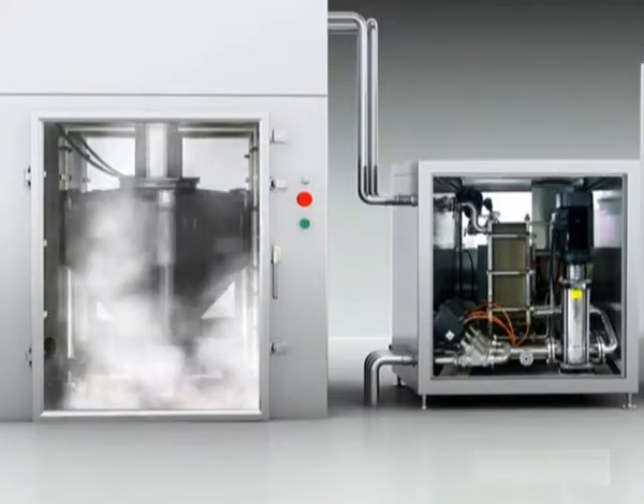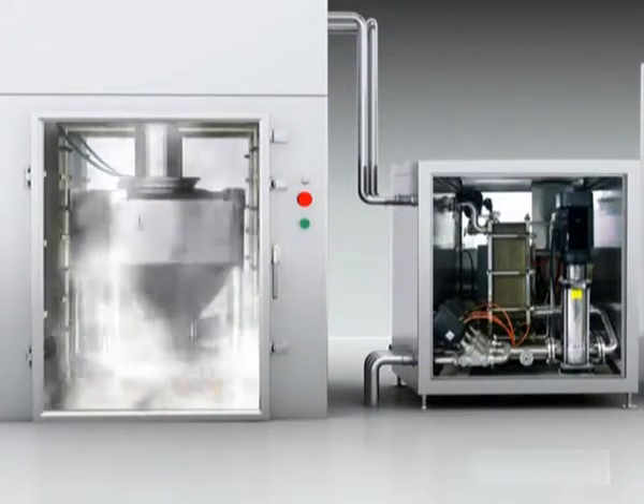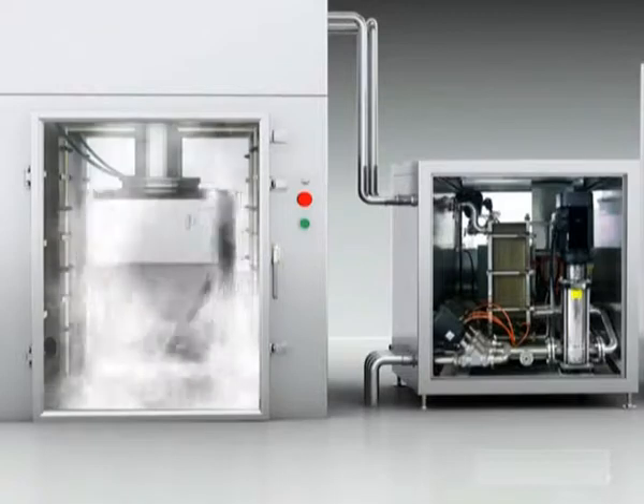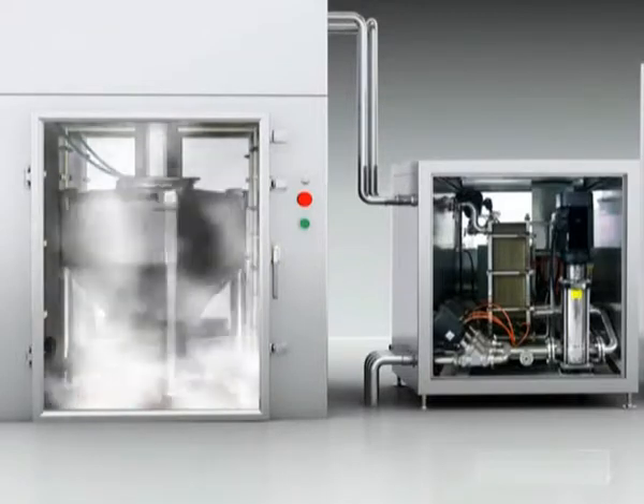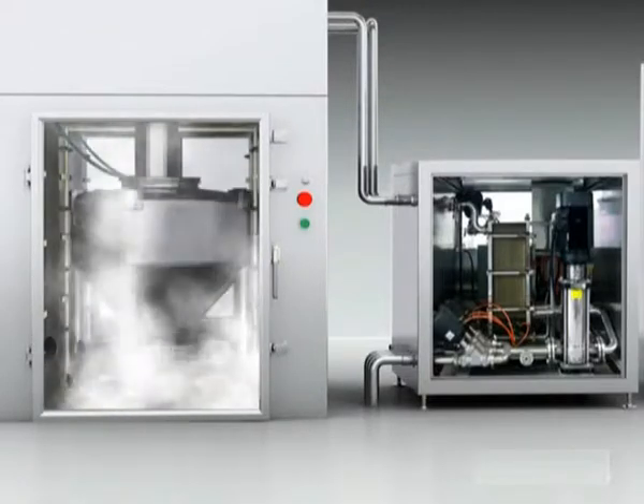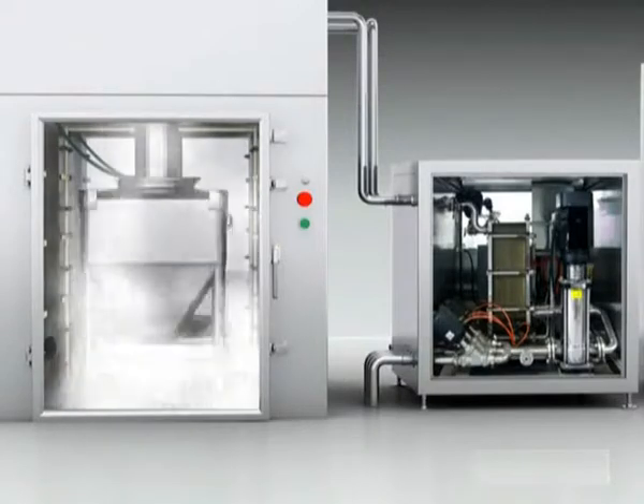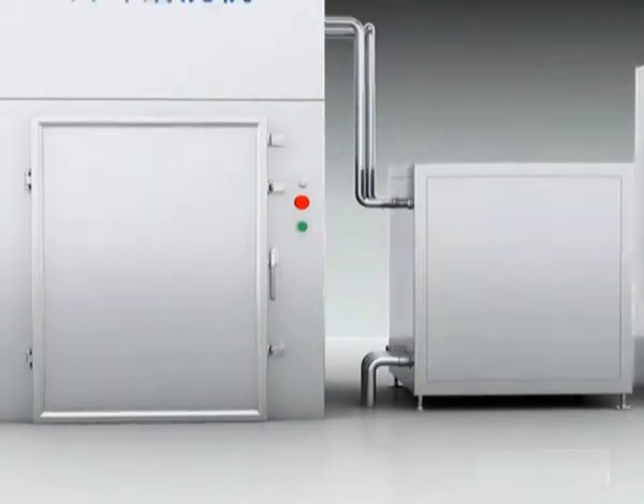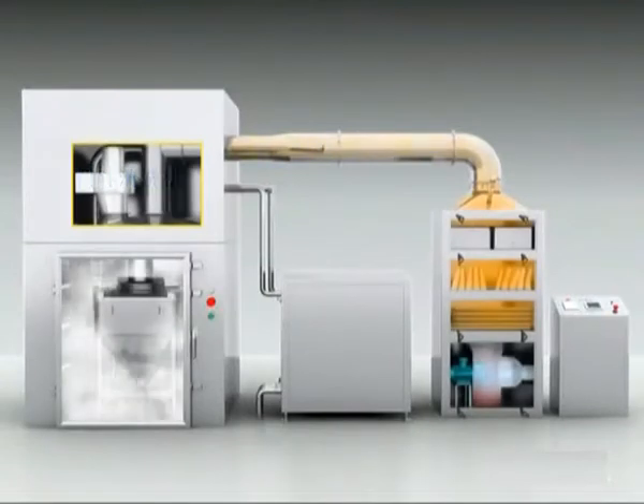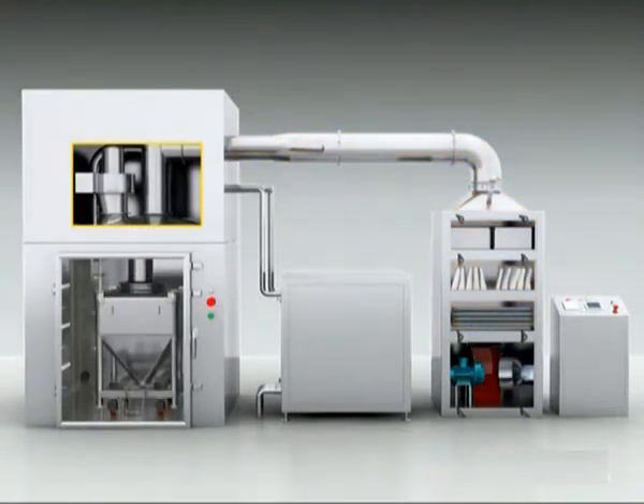Intake air is guided into the washing chamber through the primary filter, medium filter, heat exchanger, and HEPA filter by the air fan. The bin is then dried by the hot air blowing from the upper and lower inlets. Air cooling follows as the final process upon finishing the drying procedure. Intake air is guided into the washing chamber through a filter by the air fan. The bin is then air-cooled by the air blowing from the upper and lower inlets.